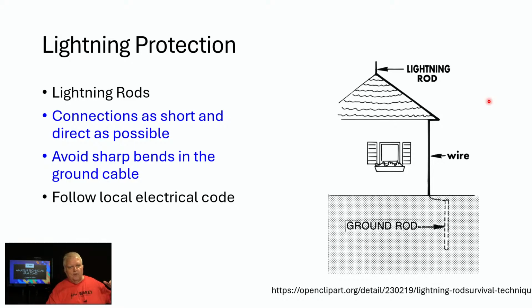And so if it's going along a wire in a straight line and all of a sudden the wire goes off at a 90-degree angle, that plasma ball might just continue going in a straight line and hitting whatever is in its way and damaging it severely. So that's why we say to avoid sharp bends in ground cables used for lightning protection. And you want to follow the local electrical code.